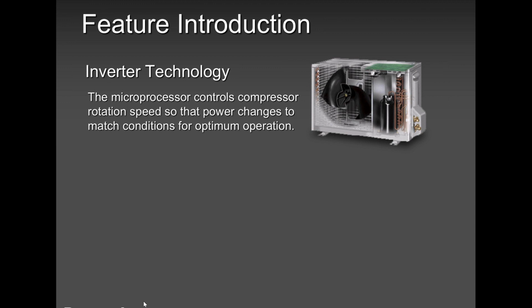Inverter technology is simply a microprocessor that controls the compressor. That compressor there is driven by three-phase voltage, okay? Three-phase AC voltage. That compressor there ramps up and down depending on the supply of that voltage. When the three-phase voltage supplied to the compressor is high, the compressor is running at a higher frequency. When it is supplied with three-phase, a lower voltage like 48, 50 volts between U, V, W, the compressor is running at a lower frequency.